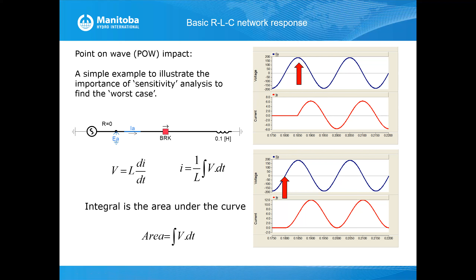Now, when you're performing a study, the breaker logic does not get closed at any moment. It can actually close at any moment along the cycle. So depending on where in the cycle you are closing the breaker, your network will experience different transients. So point-on wave is an extremely important study for certain situations.